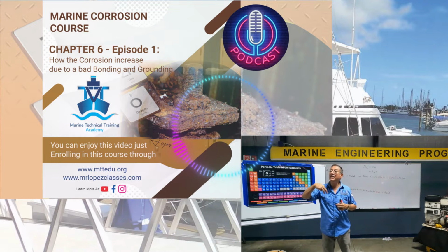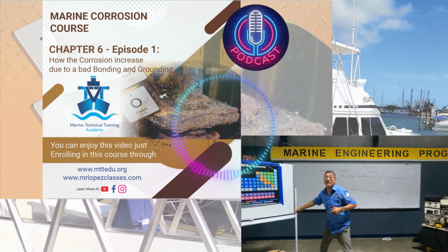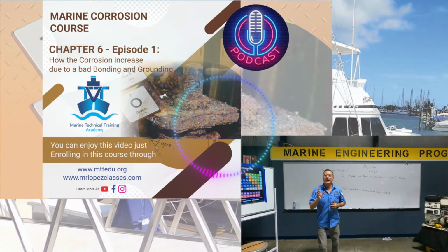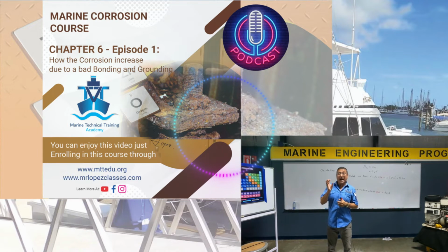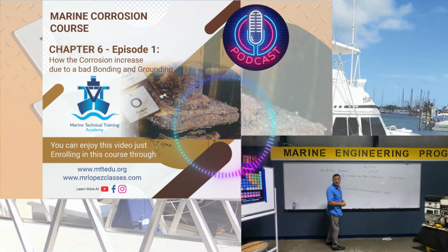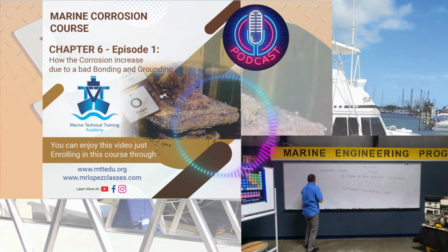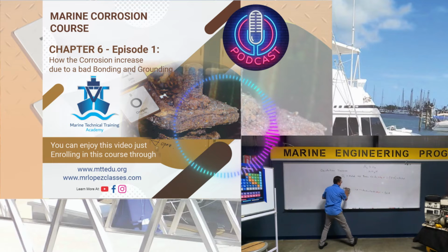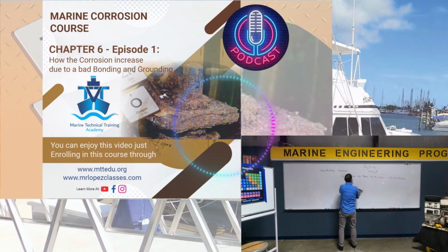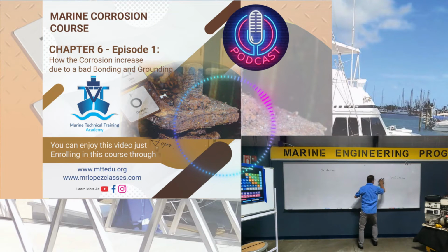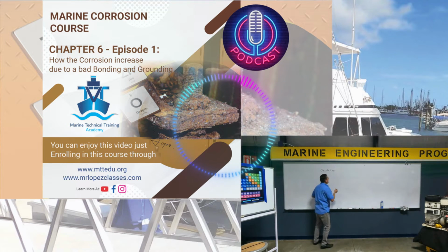bar in AC, with the negative bus bar in electronics, with the main negative bus bar of the DC, all of them shall be connected with the bonding conductor, and the bonding conductor to the zinc. Once again, the negative of electronics, the negative bus bar of the DC panel, the ground bus bar on the AC panel, all of them shall be connected at the end with the bonding conductor, and the bonding conductor finishes into the zinc. This is mandatory.